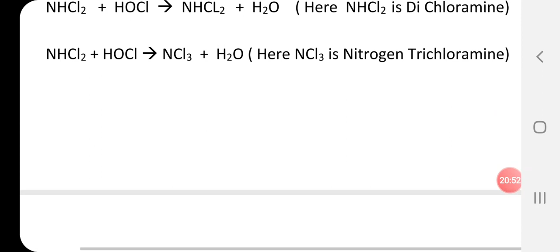How all these chloramines act in the water depends on the pH of the water. Monochloramine predominates at a pH value of over 7.5, dichloramine is predominant in the range of pH 5 to 6.5, and nitrogen trichloramine is prominent in the range below pH 4.5. So they act at different pH levels: monochloramine above 7.5, dichloramine between 5 and 6.5, and trichloramine below 4.5.